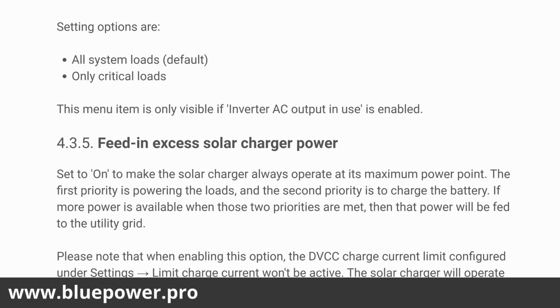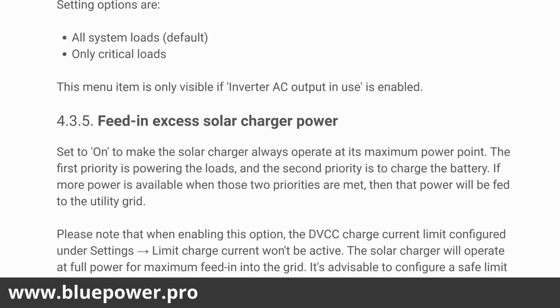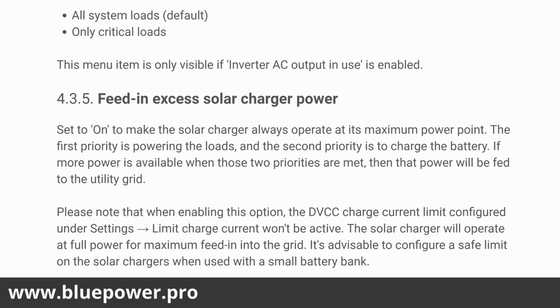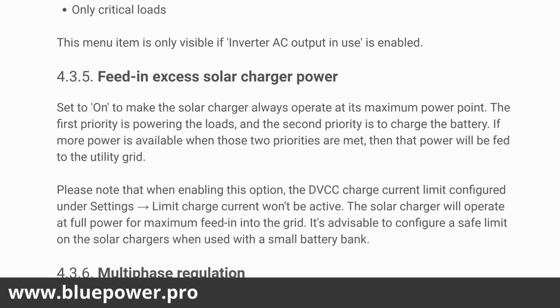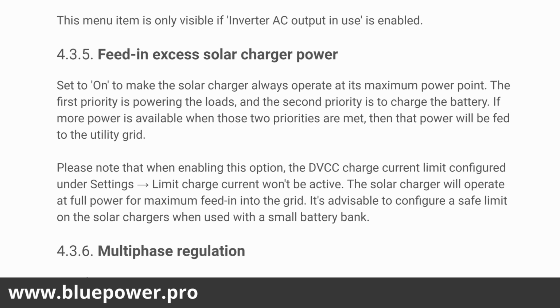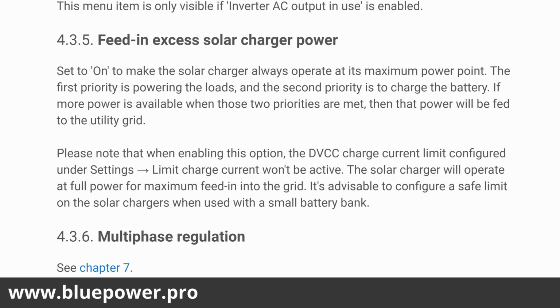You can also limit the inverter power. That's in the newer firmware, limit the inverter power. So that's only going to be applied when the inverter is connected to the grid, that limit. Then we've got the feed-in excess solar power. So over there we can set to feed in our excess AC solar power or excess DC solar power. That's also where you go and see if the firmware's communication is operating correctly. There it will indicate feed-in active is going to be indicated as yes if the firmware is connected to the system.